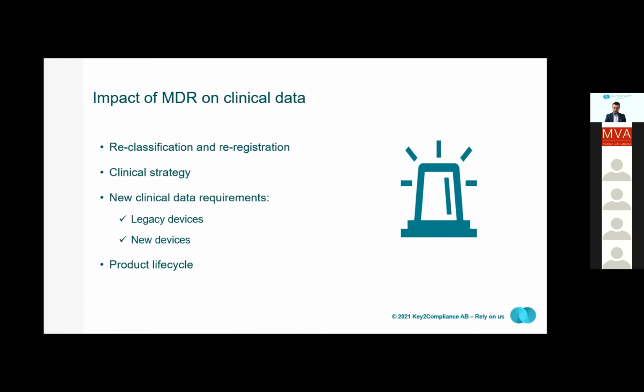So MDR will require a reclassification and re-registration of all medical devices currently on the market. Many devices will be reclassified to a higher device class, impacting their clinical data requirements. A new product should have a clinical strategy in place in accordance with MDR. And this usually is described as a clinical development plan, which is part of the clinical evaluation plan.